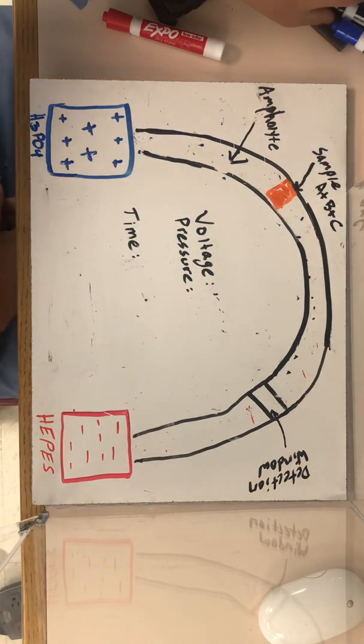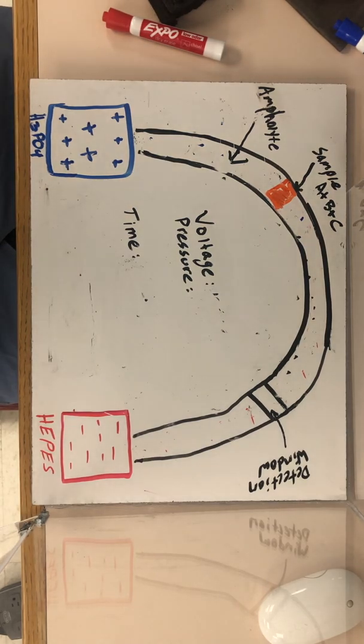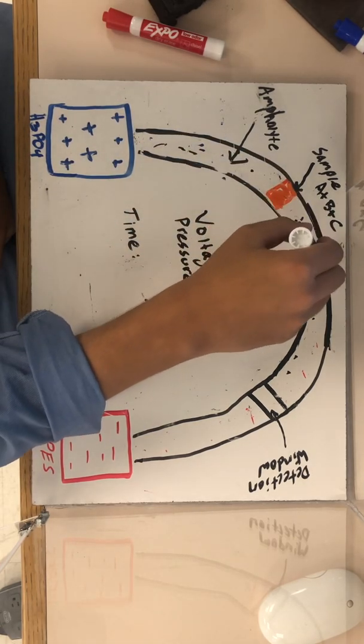Okay, I'm beginning this model of how to do a capillary isoelectric focusing run. In the first step of any capillary isoelectric focusing run, the first thing you're going to do is fill up your capillary with ampholyte.